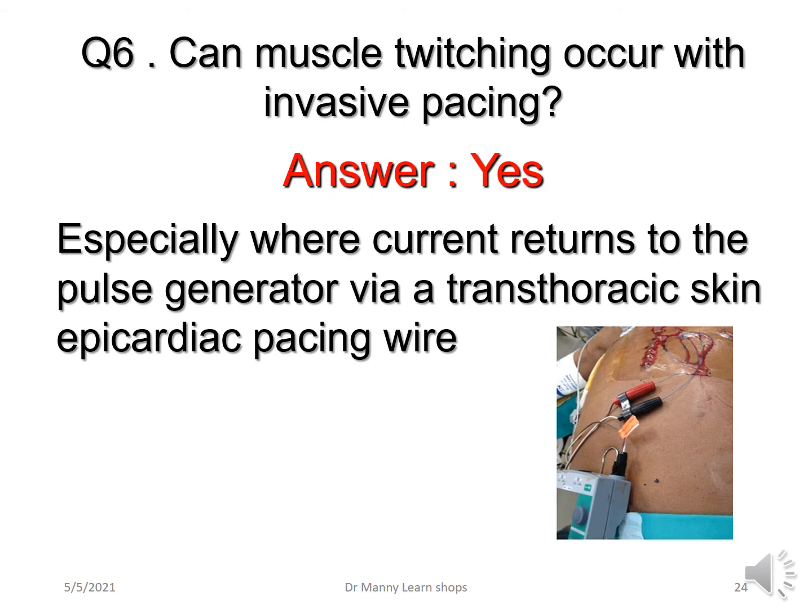Can muscle twitching occur with invasive pacing, not just transcutaneous pacing? The answer is yes, especially when the current returns to the pulse generator via a transthoracic skin or epicardial pacing wire, often seen post-cardiac surgery, open chest surgery or heart surgery.